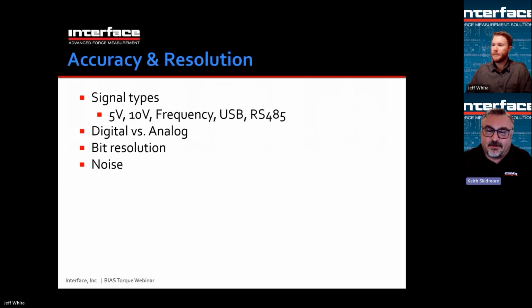So, very typical signal types: 5 volt, 10 volt. Some sensors will have a frequency output. You also have digital outputs such as USB or RS-485. Almost exclusively, and I can't think of an example that would not be, torque sensors are bipolar. If it says it's got a 5 volt output, what that really means is it measures plus or minus 5 volts. It measures 0 volts at 0 torque, and then under a clockwise torque, it goes from 0 to plus 5 volts, and under counterclockwise torque, it goes from 0 to negative 5 volts. So there's really not a case I can think of where it would only work in the clockwise direction.